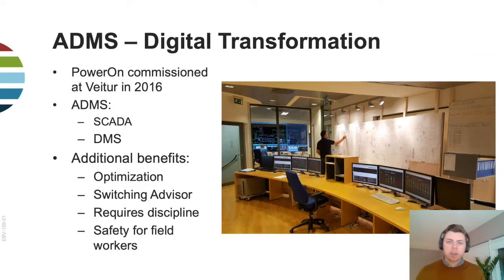Our ADMS, Advanced Distribution Management System, was commissioned at Veitur in 2016. Our product contains both the SCADA and the DMS, and as you can see, it was a pretty big step from what we had before. Before, we only had the feeders at the primary substations in a digital representation for real-time operation, and the secondary substation was simply a pin on a whiteboard. But now we have a digital representation of the high and medium voltage, but not the low voltage.